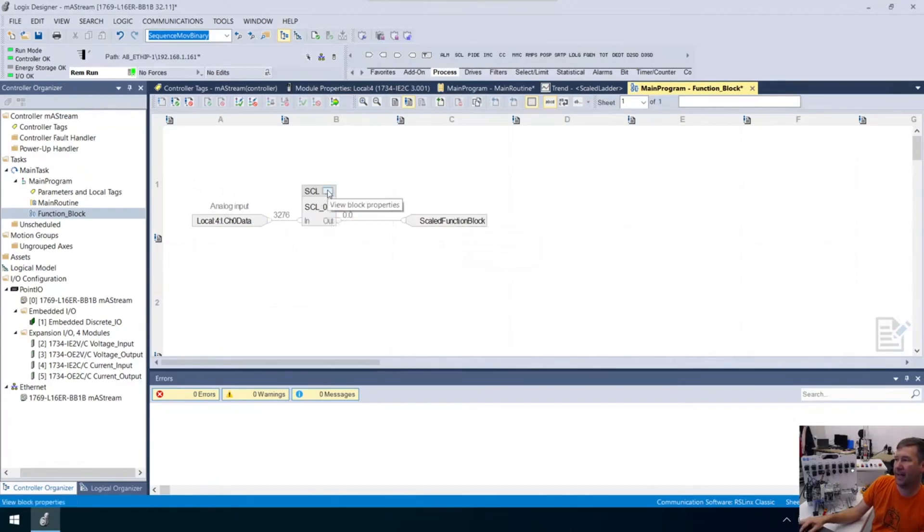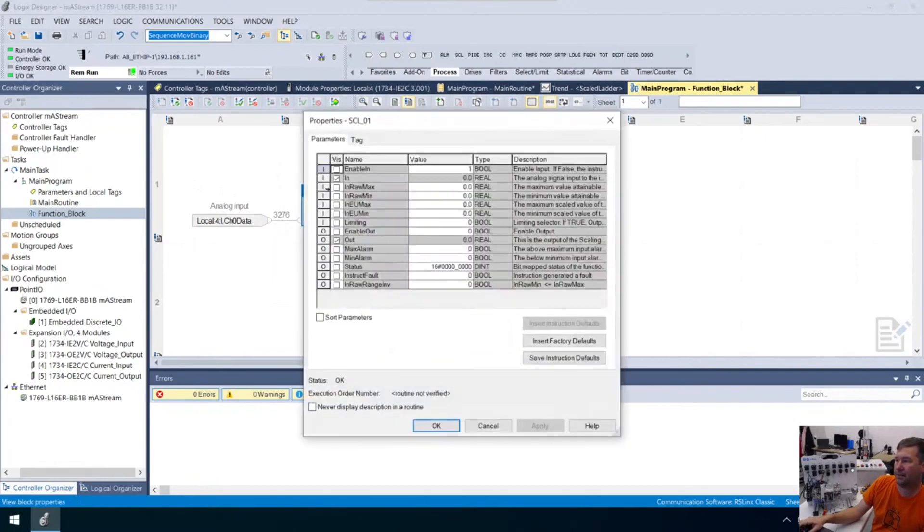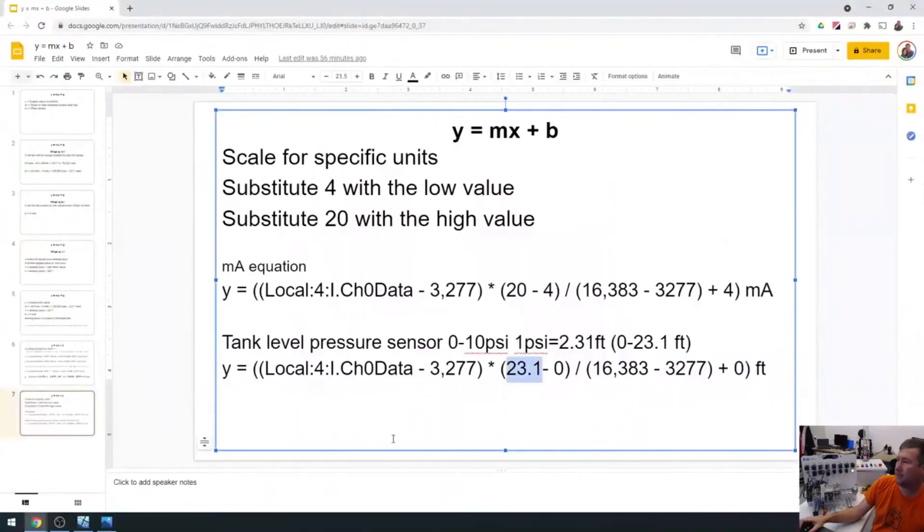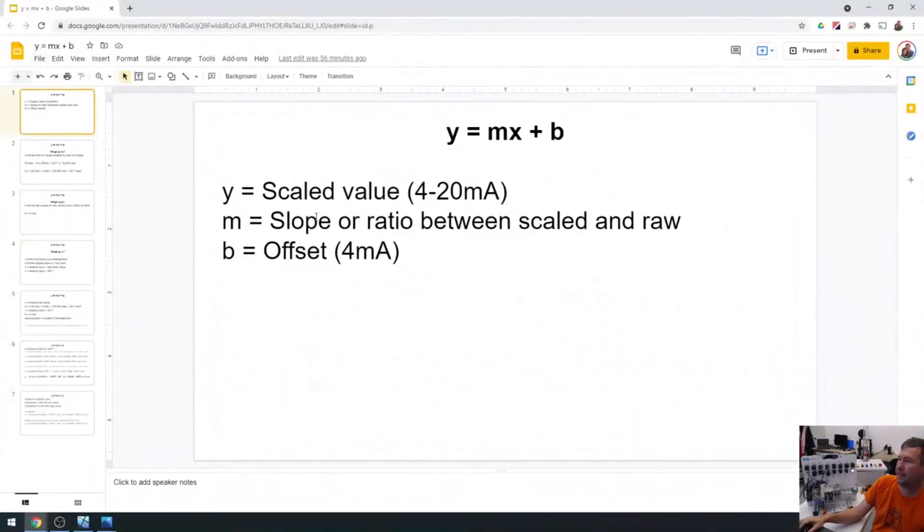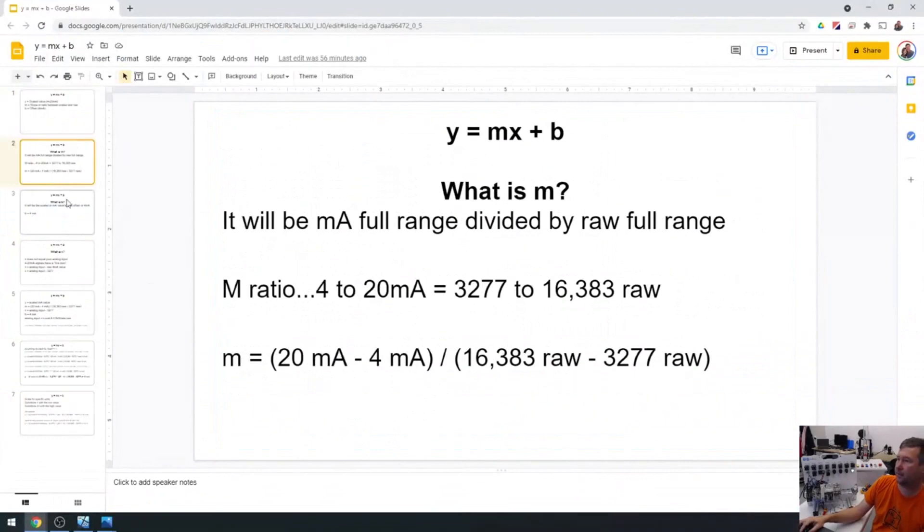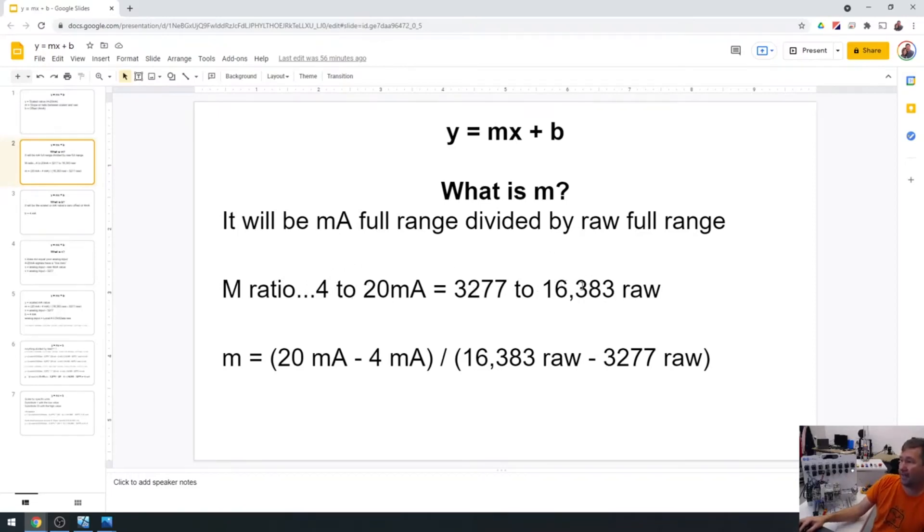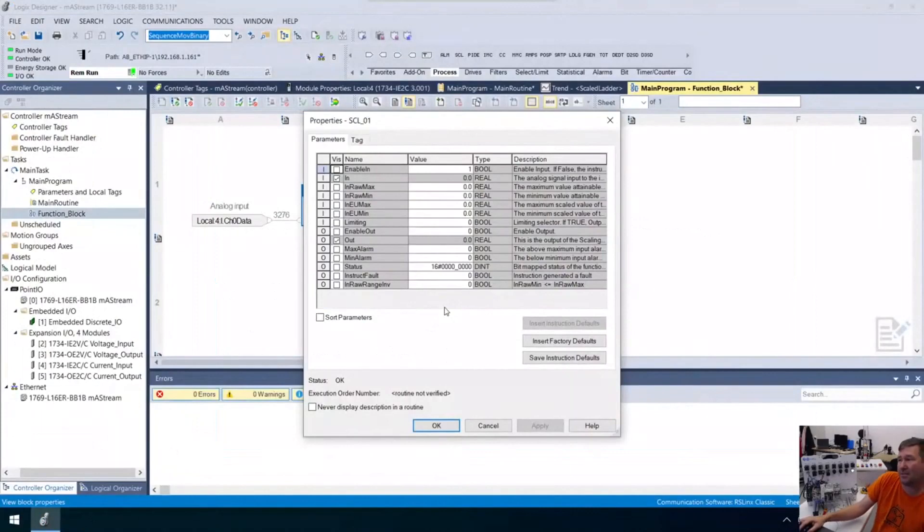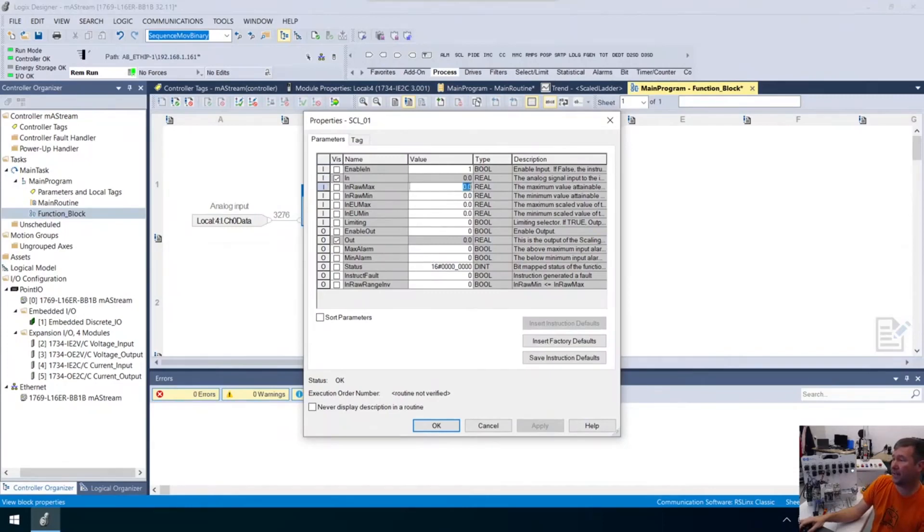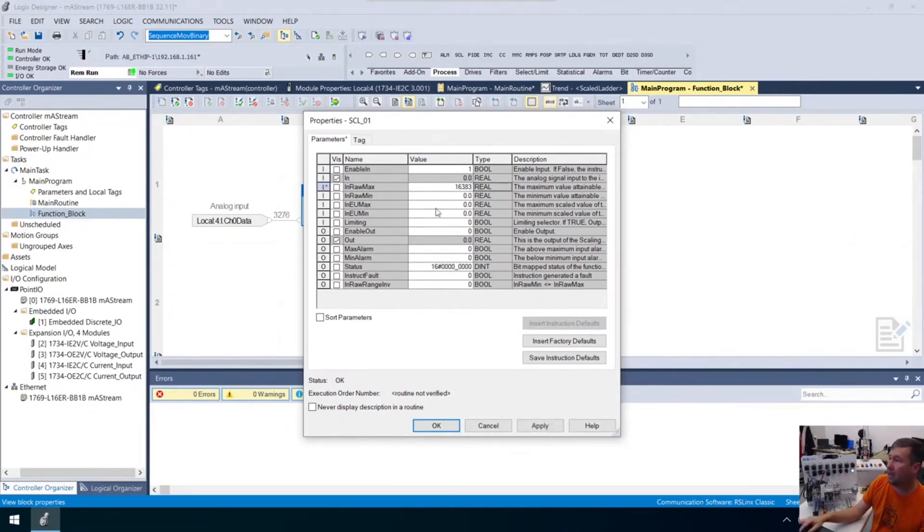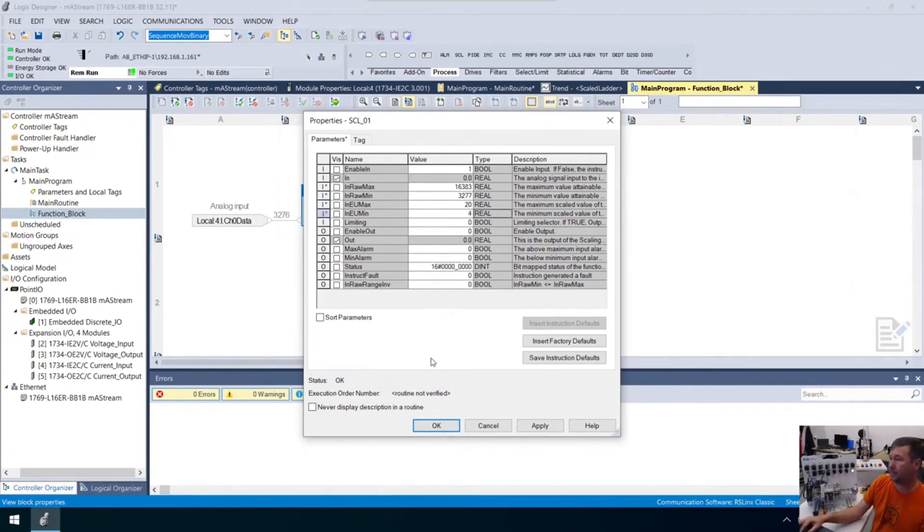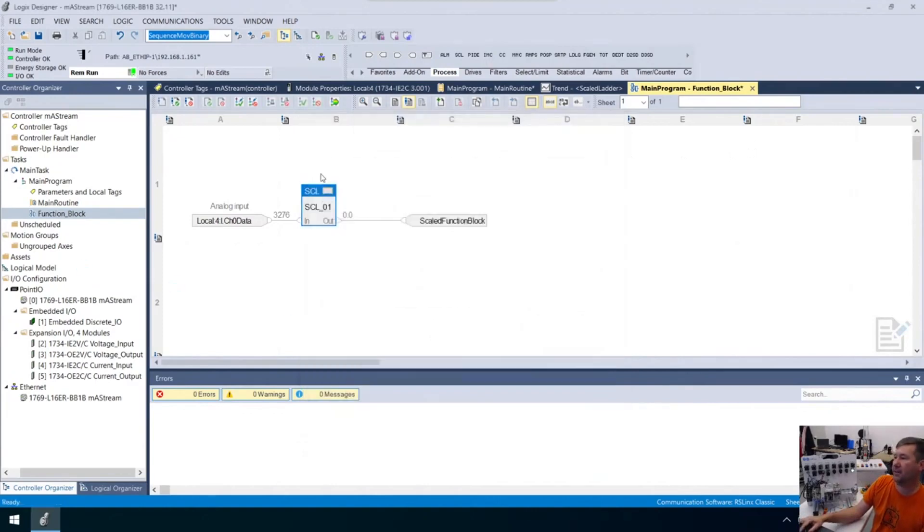This is going to take our analog input and scale our function block. We have block properties and we see we have raw max, raw min, engineering units max, and engineering units min. We know that our 4 to 20 equals 3,277 to 16,383. These are those numbers. Our raw max is 16,383, our raw min is 3,277, our engineering max is 20, our engineering min is 4. Let's start by just throwing that in.